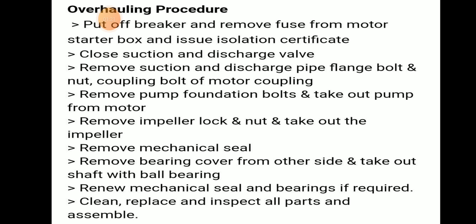To summarize the overhauling steps: put off the breaker, remove the fuse from the motor starter box, and issue an isolation certificate. Close suction and discharge valve. After closing, remove suction and discharge pipe flange bolt and nut, and coupling bolt of motor coupling. Remove pump foundation bolt and take out the pump from the motor.